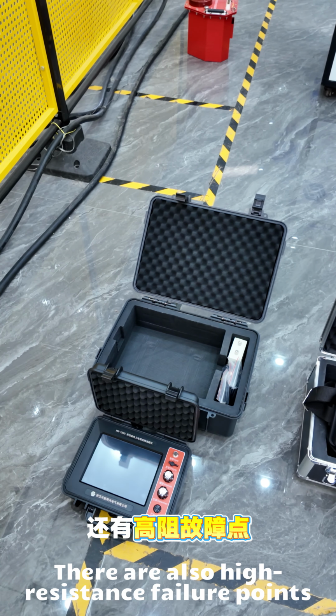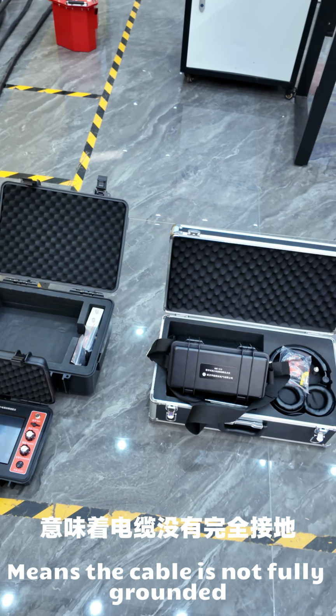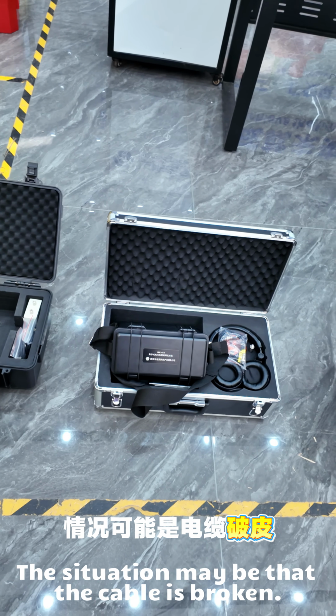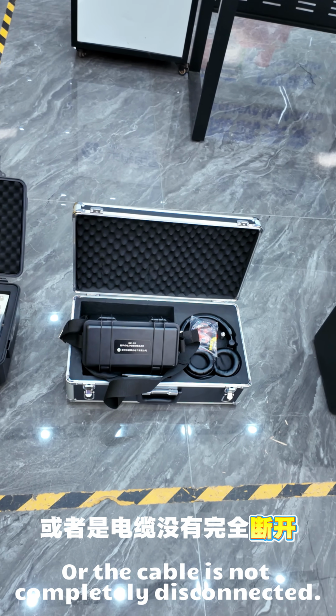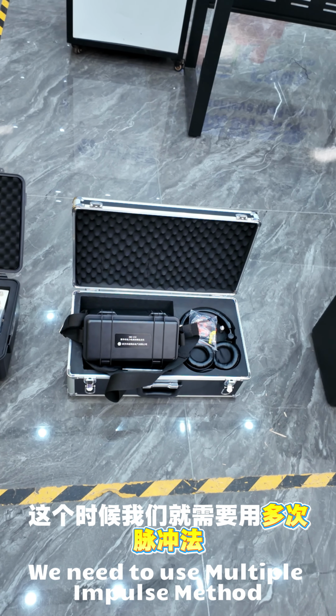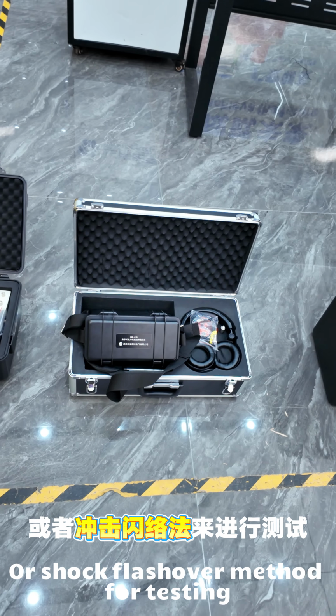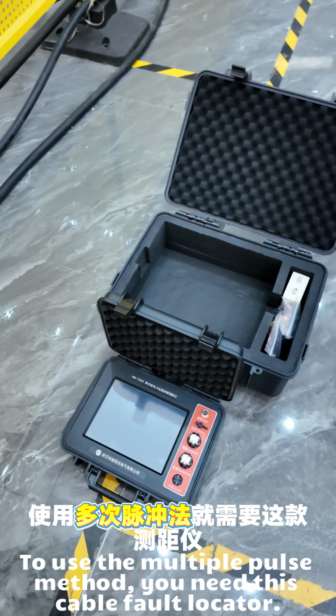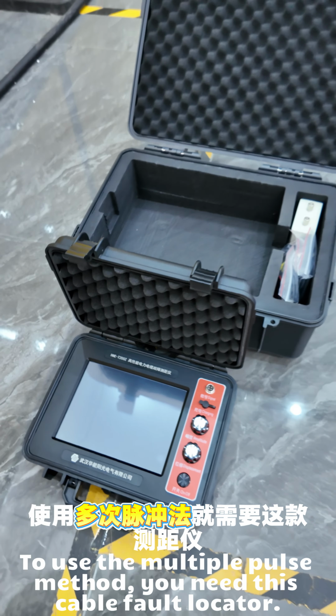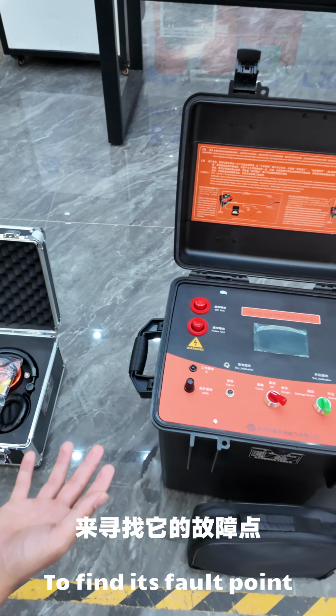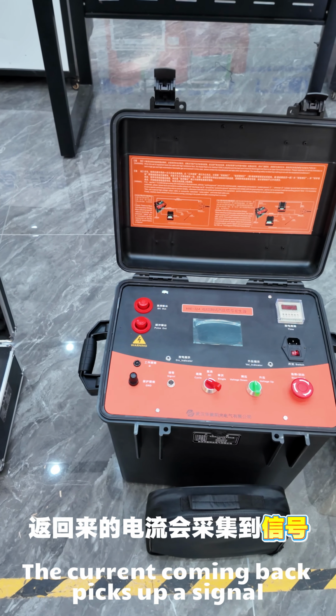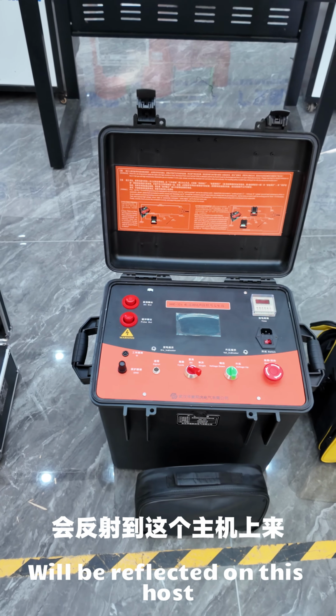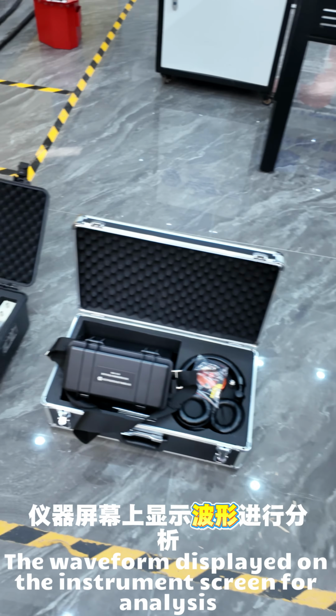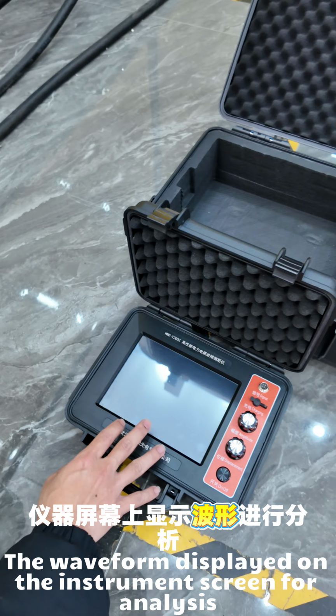There are also high-resistance failure points, which means that the cable is not fully grounded. The situation may be that the cable is broken, or the cable is not completely disconnected. We need to use the multiple impulse method, or shock flashover method, for testing. To use the multiple pulse method, you need this cable fault locator to find its fault point. When you use multiple pulses, the current coming back picks up a signal, which will be reflected on this host, and the waveform is displayed on the instrument screen for analysis.